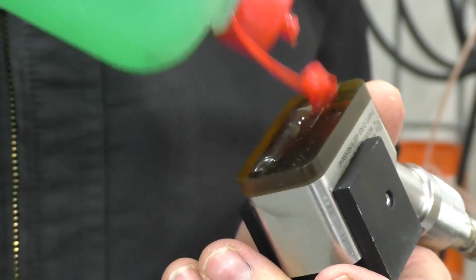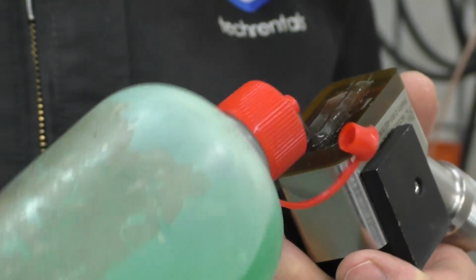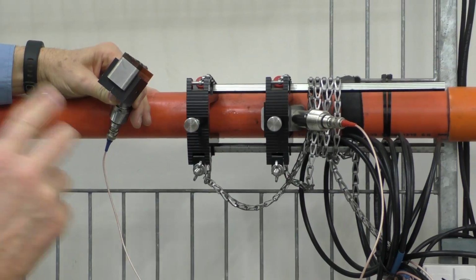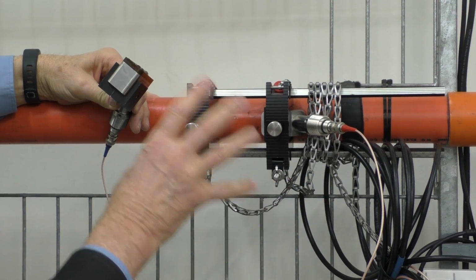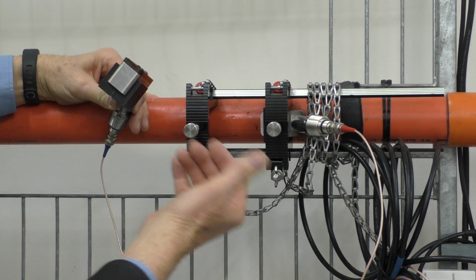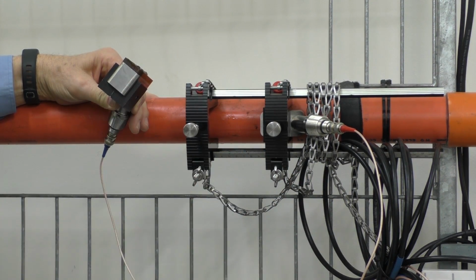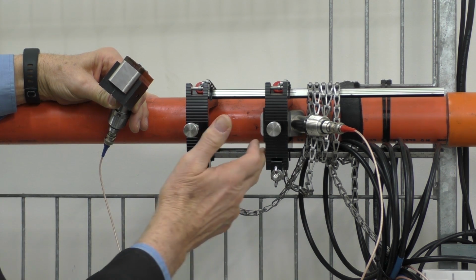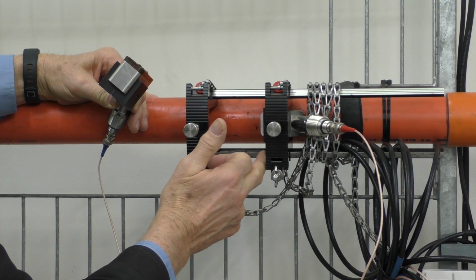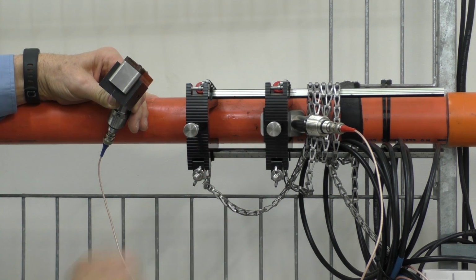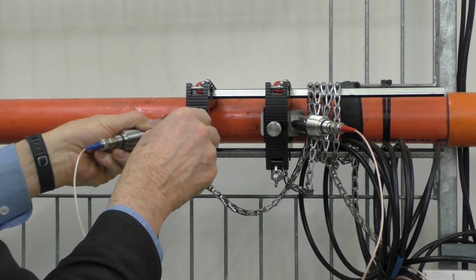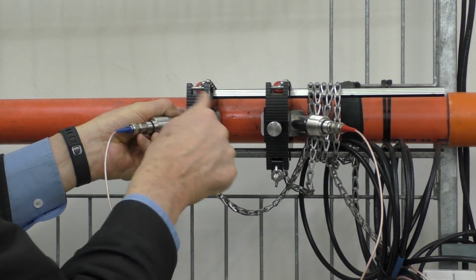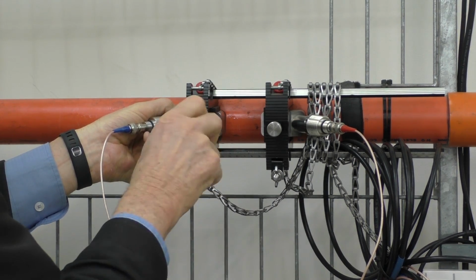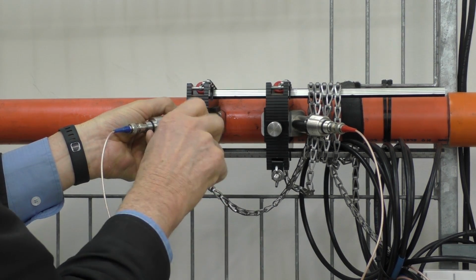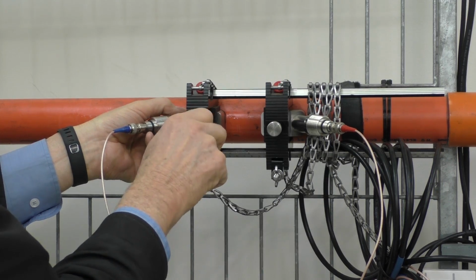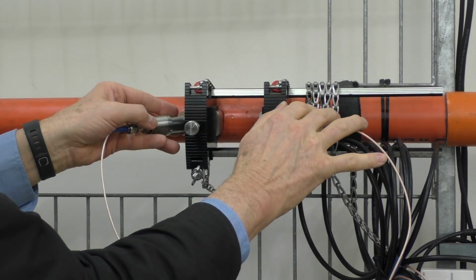We apply some couplant to the transducer, just a thumbnail worth. This is the older style rig. It's very similar to the newer one. The new one's a little better. Instead of having screws, it's got clamps. So we've set this rig up to the spacing that the program specified, and we put both transducers in. So I lock that in place. The newer one has a much nicer mechanism. So we lock this in place.